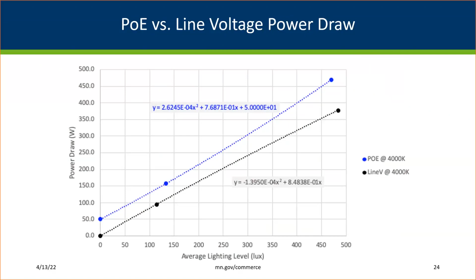Upon examination of power use profiles at different points in the year for each classroom's lighting system, PoE power consumption is consistently higher than the traditional AC lighting system. At an average lighting level of 470 lux for each of the classrooms, the power for the line voltage fixtures was about 360 watts, while the PoE lighting system was about 460 watts. The power to the original lighting system of the 2x4 troffers with T8 lamps was about 1200 watts. So both LED systems provide a significant power reduction over the original T8 lamps.